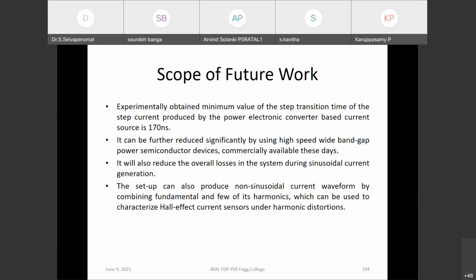The setup can also produce non-sinusoidal current waveform by combining the fundamental and a few of its harmonics, which can be used to characterize Hall effect current sensors under harmonic distortion. It will also reduce the overall losses in the system during sinusoidal current generation.